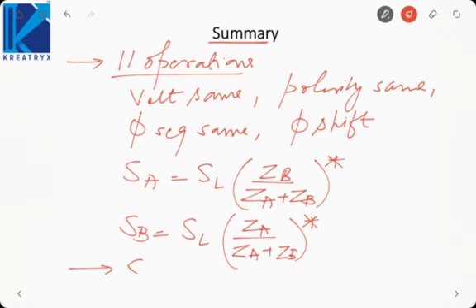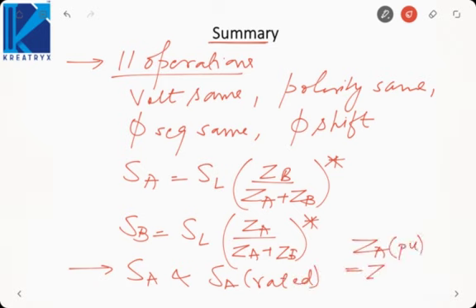And if we say SA is proportional to SA rated, that is, load sharing is proportional to KVA rating, then ZA per unit must be equal to ZB per unit, where per unit values are on their individual bases. And last we saw Sumpner's test, which estimates the temperature rise in the machine by operating it at rated voltage and rated current, so that core and copper losses are encountered simultaneously and not under separate conditions. So this is all about parallel operation. In the next lecture, we will be dealing with auto transformers.